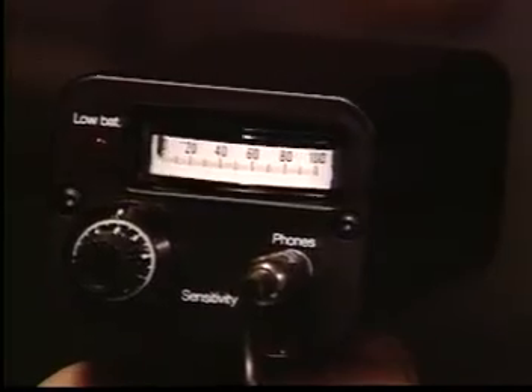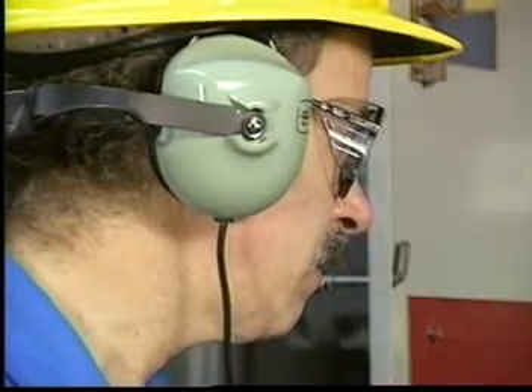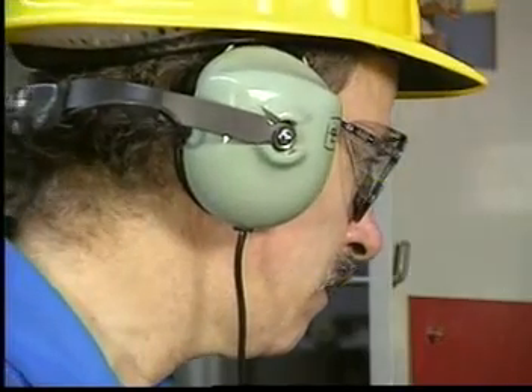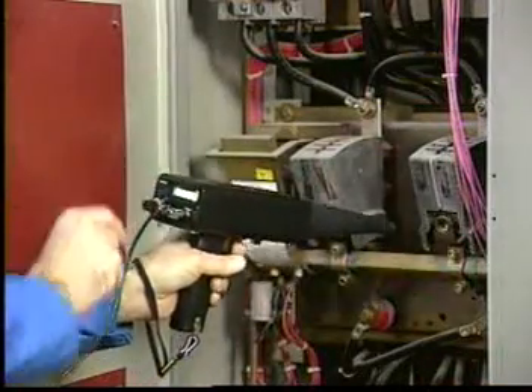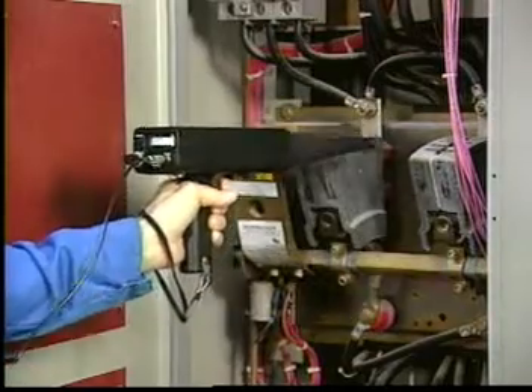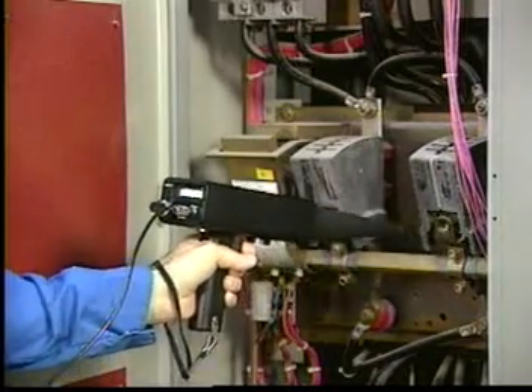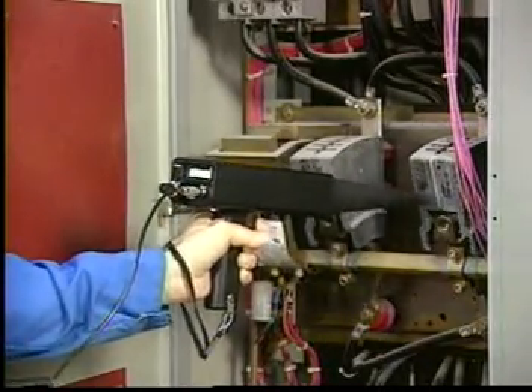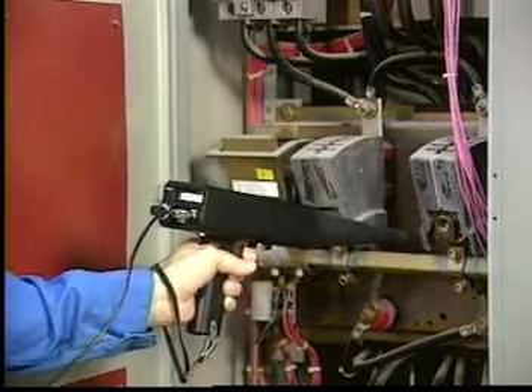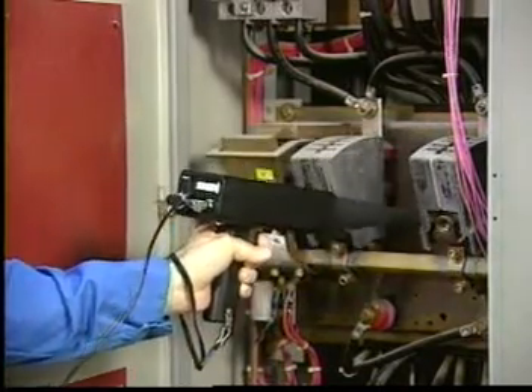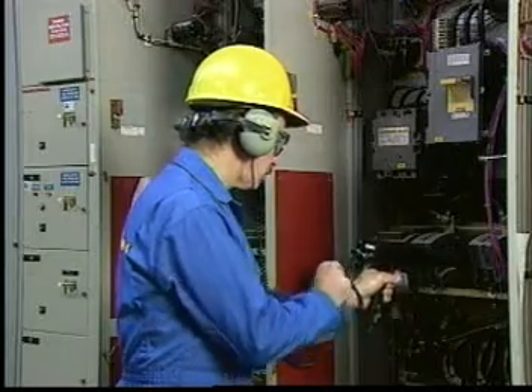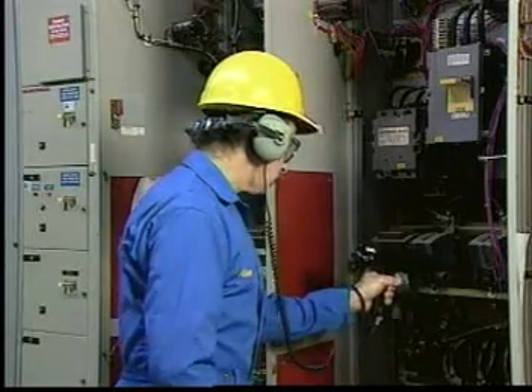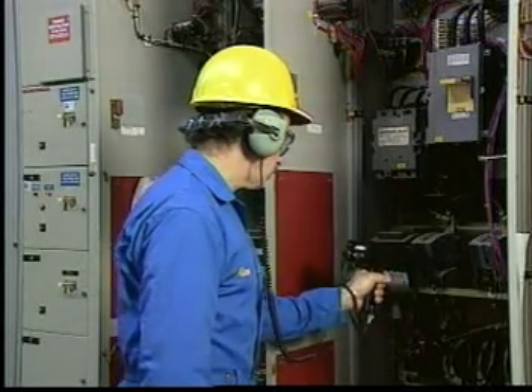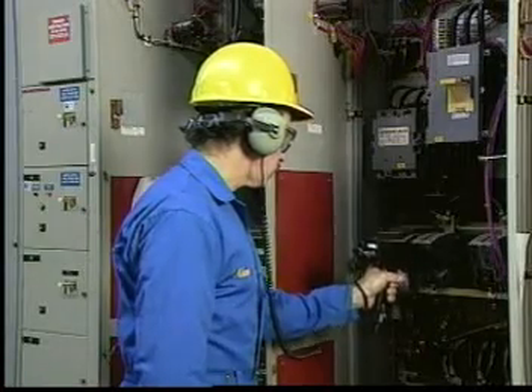Follow the ultraprobe by watching the meter and listening for the loudest point. Once the leak has been located, confirm the site by moving the probe back and forth in all directions, maintaining a safe distance. You will note that the sound level increases as you pass over the leak site. These steps are all you'll need to locate most electrical discharge. At this point, you may investigate further using other complementary technologies.